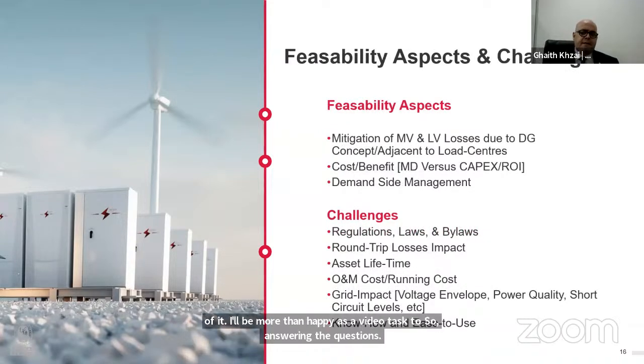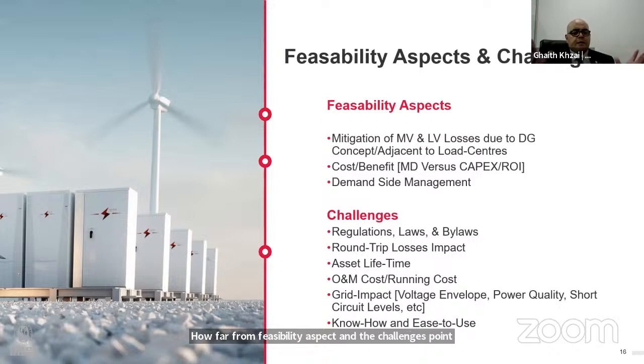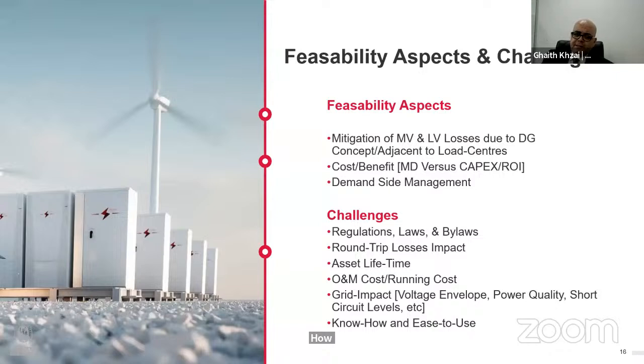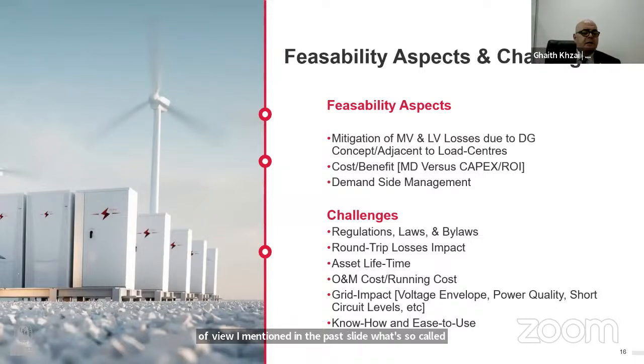However, from the feasibility aspect and the challenges point of view, we have the following. It really mitigates the medium voltage and low voltage losses, because the power flow will come from the battery. I will not import power or energy from far away on the transmission and generation side. It is nearby and adjacent to the load center, so the losses will be less. Also, from a cost benefit point of view, I mentioned in the past slide the so-called maximum demand tariff, which is a very high electricity price. When you compare the maximum demand bill versus the capex and the ROI of this investment, you will find it is feasible, and the rate of return will be really fast, maybe below 5 years in many cases.